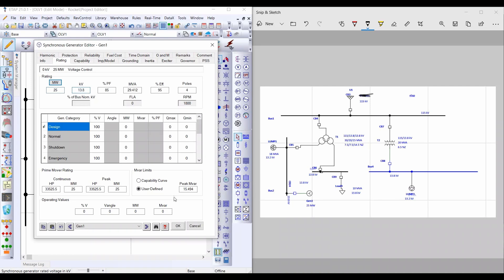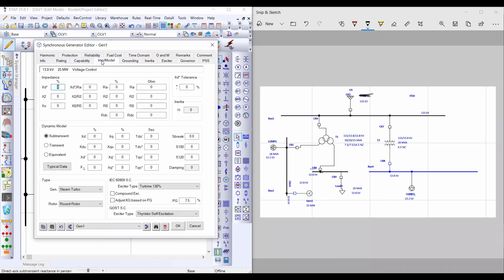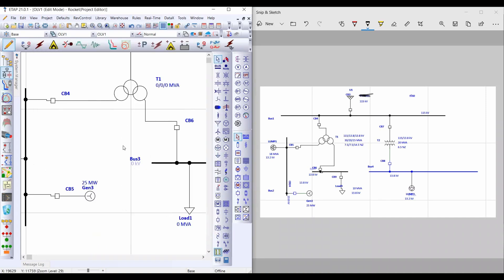From here, insert the power that you will take from this generator. In this example, I will take only 4 MW. From MVar Limit, select User Defined and set Q maximum to 10. From Impedance, select Typical Data, then click OK.